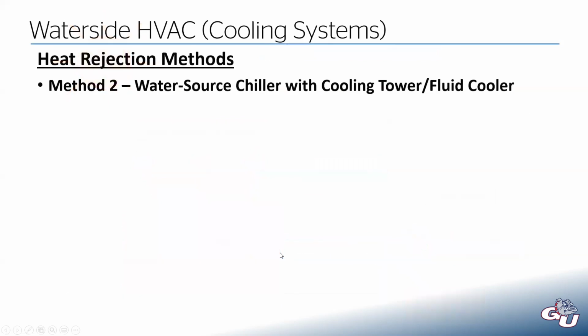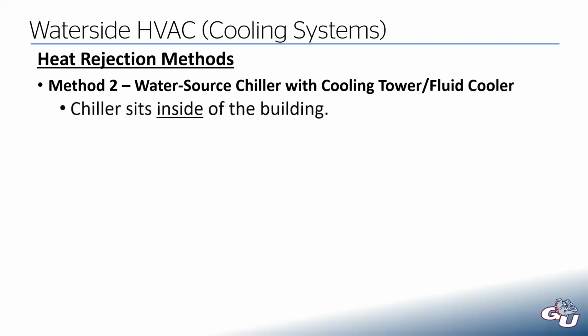But that brings us to the second method, which is a water source chiller. Before we were talking about an air source system, this would be a water source chiller with a cooling tower, or could also be called a fluid cooler. There are some differences between a cooling tower and a fluid cooler, but that's not something I'm going to get into for this class. In this scenario, the chiller actually sits inside of the building versus an air source chiller, which sits outside of the building.